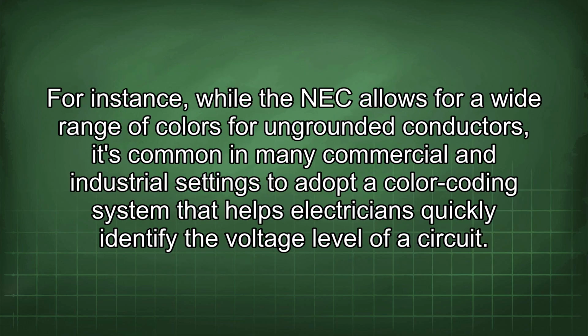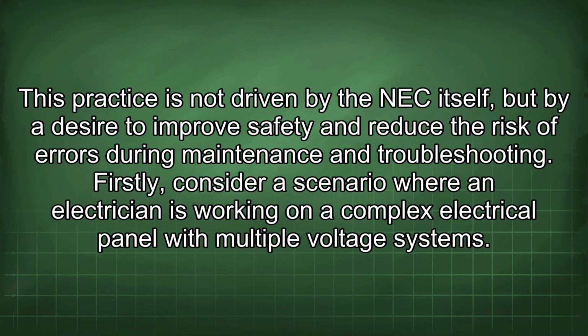For instance, while the NEC allows for a wide range of colors for ungrounded conductors, it's common in many commercial and industrial settings to adopt a color coding system that helps electricians quickly identify the voltage level of a circuit. This practice is not driven by the NEC itself, but by a desire to improve safety and reduce the risk of errors during maintenance and troubleshooting.